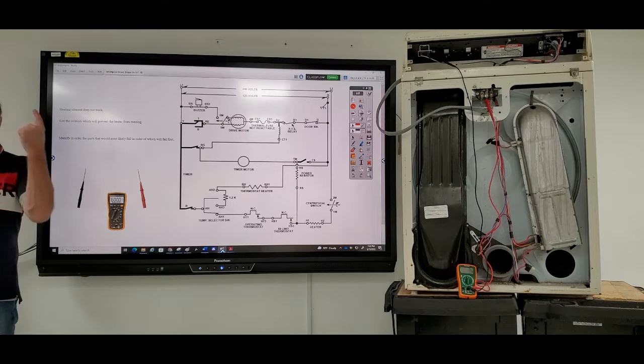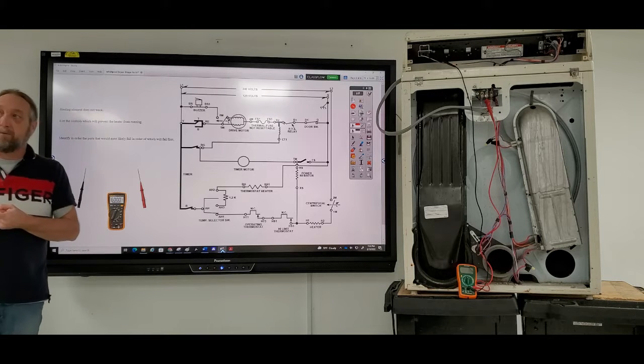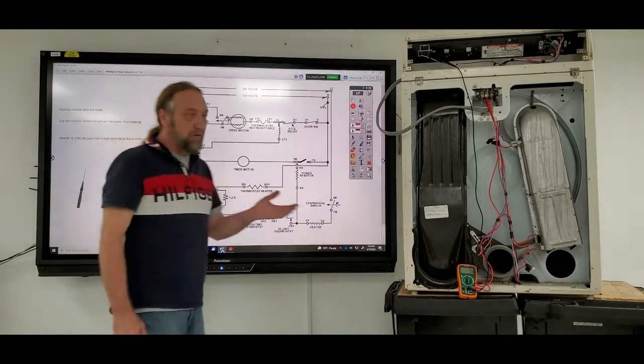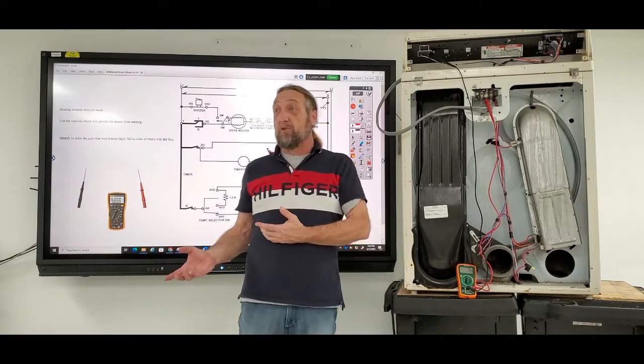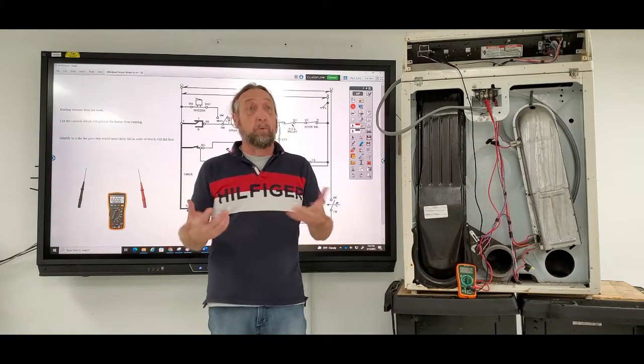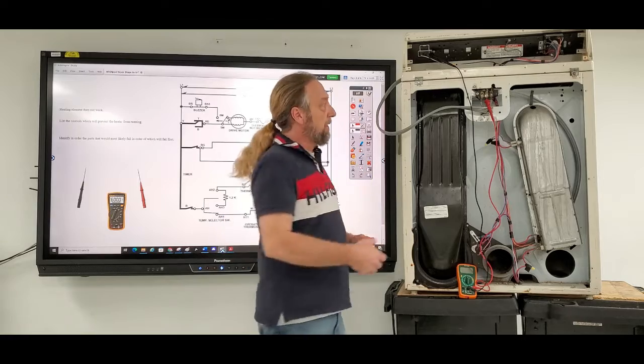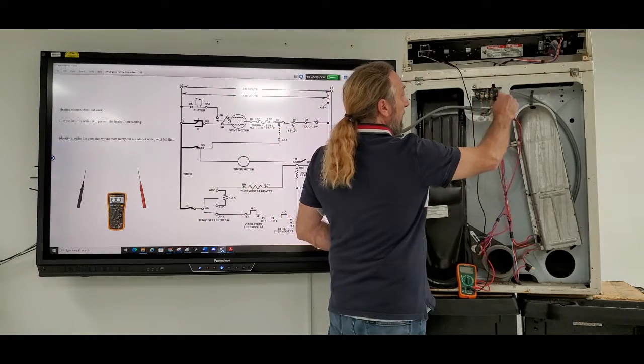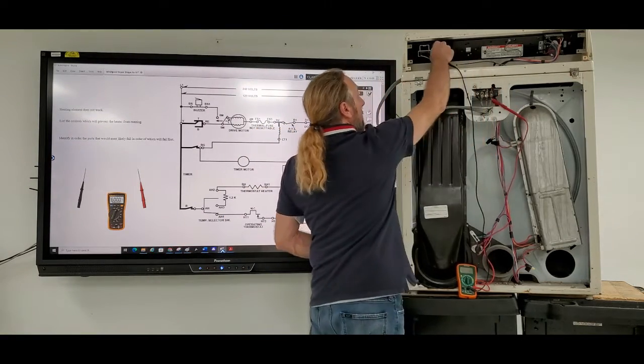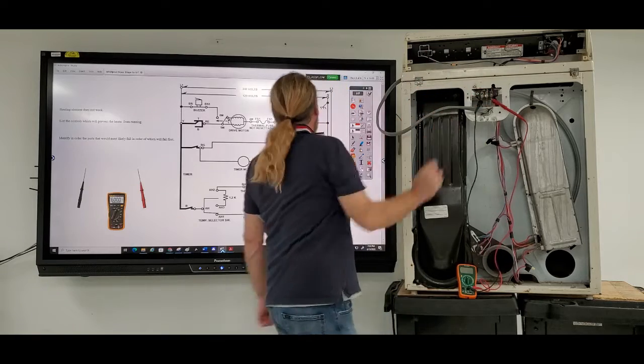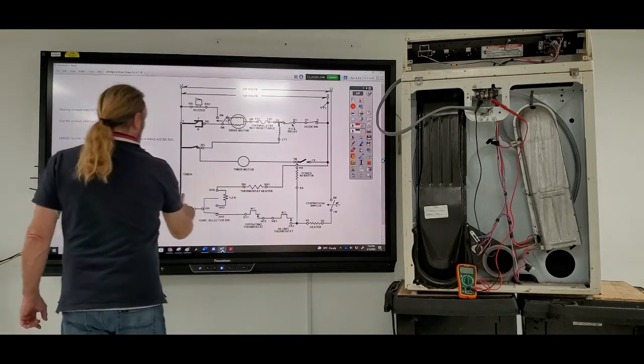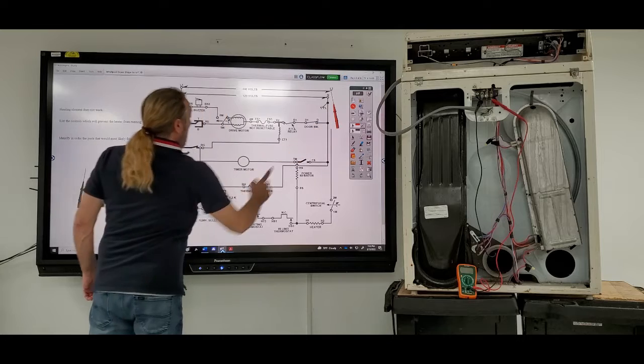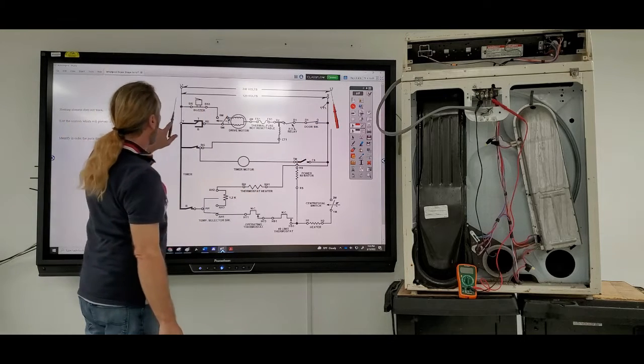Okay, first test is what? Power. Yeah, how much power now? 240. We assume the motor's running and the heater's not working by the complaint, but we want to verify it, right? So I'm going to put one meter lead on line 2 and the other meter lead on line 1, here and here, to see if I get 240 volts.